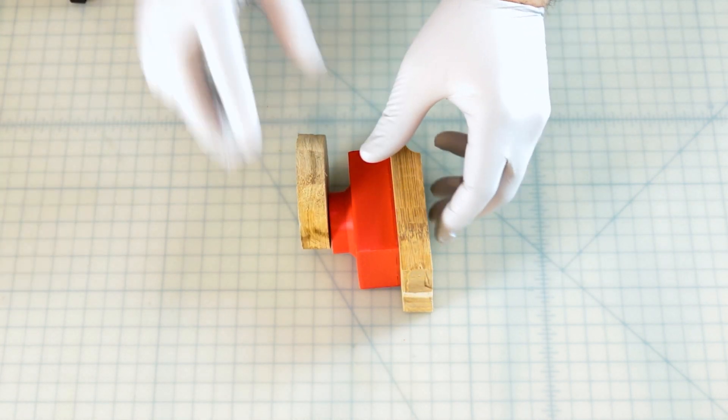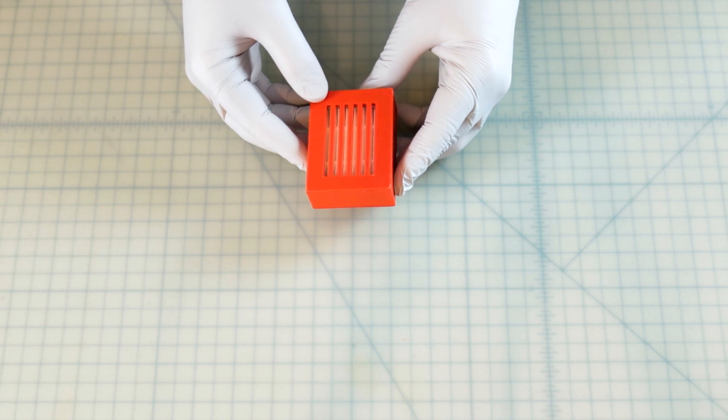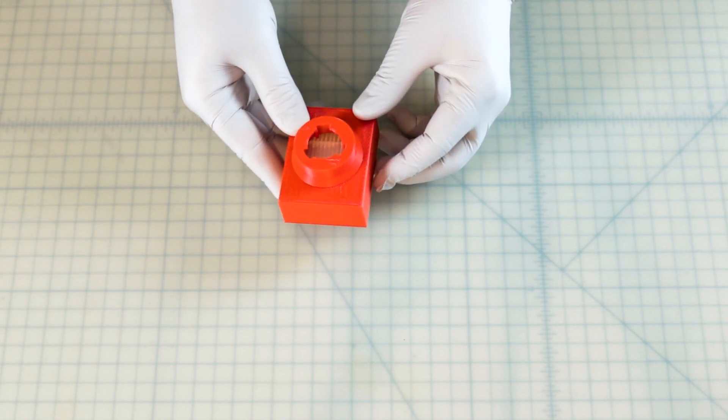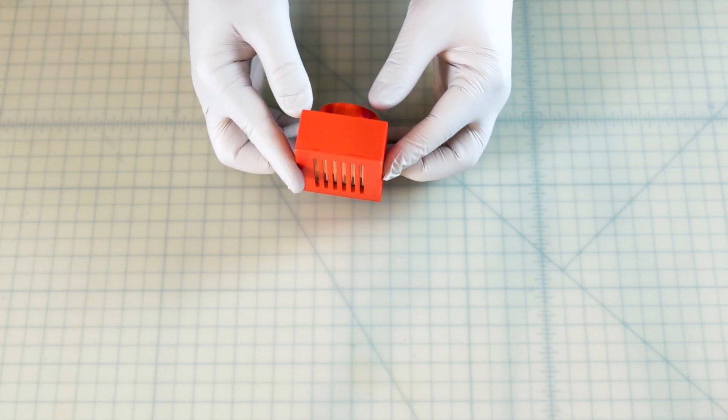Now that we have a completed product, we'll do some basic testing to ensure that we're not fooling ourselves with the effectiveness of this design. First, we'll do a limited leak test with stannic chloride to test for any gross leak. The mask passes without any major issue.